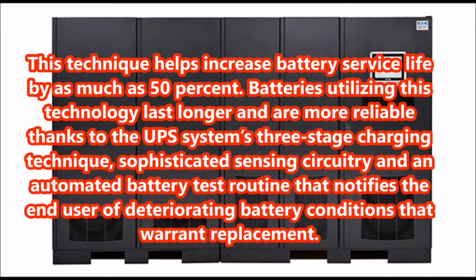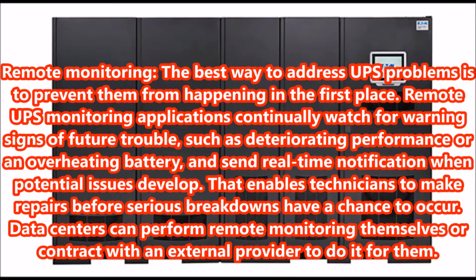Batteries utilizing this technology last longer and are more reliable thanks to the UPS system's three-stage charging technique, sophisticated sensing circuitry and an automated battery test routine that notifies the end user of deteriorating battery conditions that warrant replacement. Remote monitoring. The best way to address UPS problems is to prevent them from happening in the first place. Remote UPS monitoring applications continually watch for warning signs of future trouble, such as deteriorating performance or an overheating battery, and send real-time notification when potential issues develop. That enables technicians to make repairs before serious breakdowns have a chance to occur.